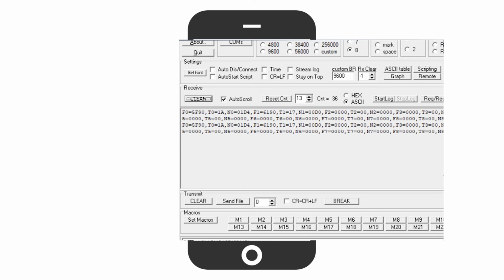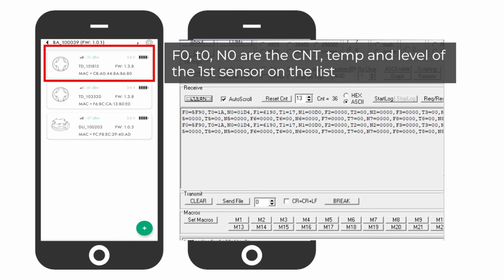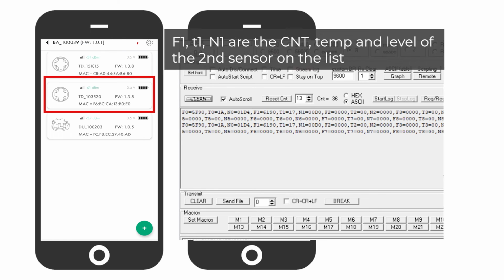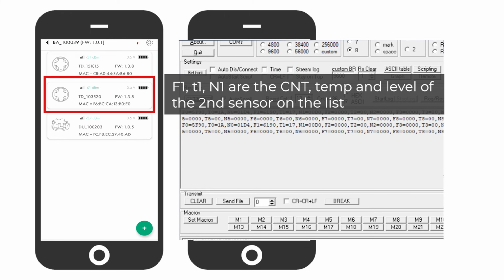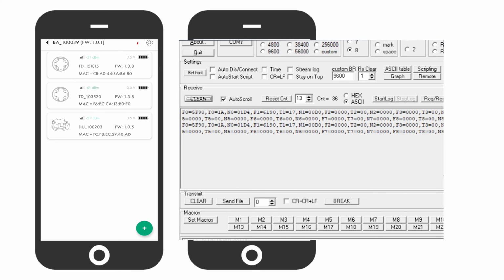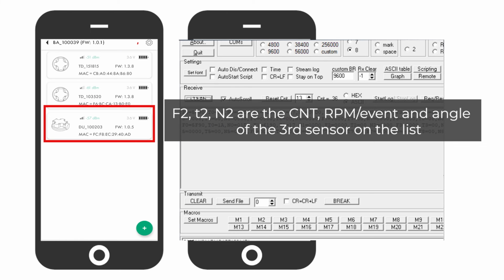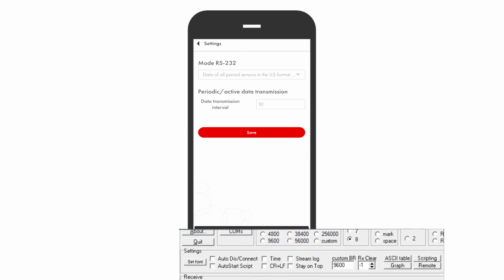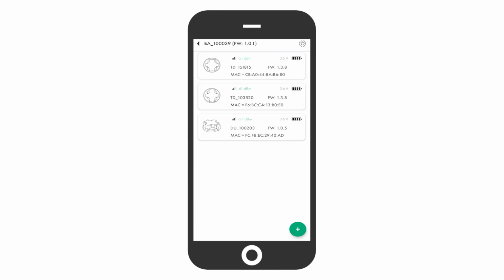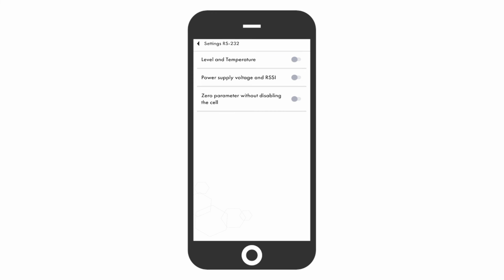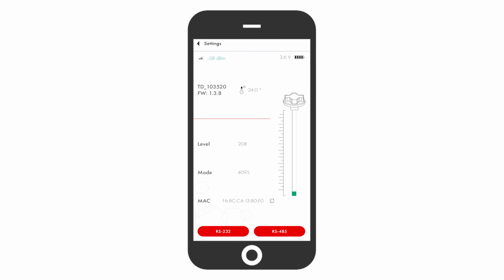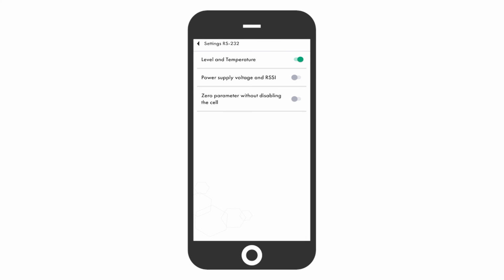If you pair a DU BLE or TH BLE, for example, the parameters will be the same, T and N, but they will be carrying an angle reading or RPM, for example, in case a DU BLE is paired with the base, or humidity and temperature readings in case the TH BLE sensor is paired with the base. And the number next to the T or N parameter corresponds to the number of the sensor's cell on the list and the menu of the base. Also, you need to open the menu of each sensor in the RS-232 settings, activate the pair of the parameters that should be included into the output string. Only one pair can be activated per each sensor.